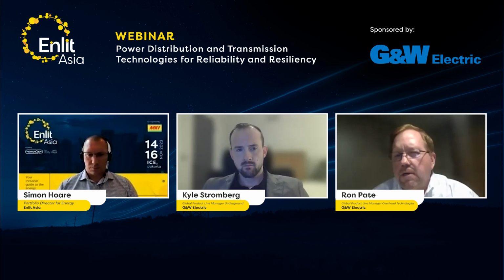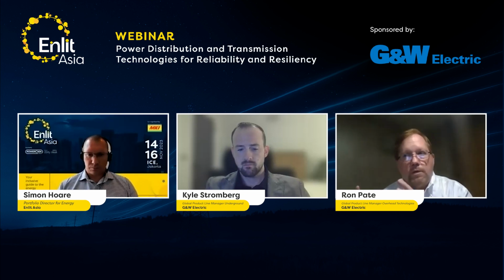Ferroresonance does happen because of the changing capacitance of your distribution system. There are ways to mitigate ferroresonance — you have to look at your substation design nearby when you go underground, and try to avoid issues like when delta transformers connect to Y. So look very carefully at your distribution planning.